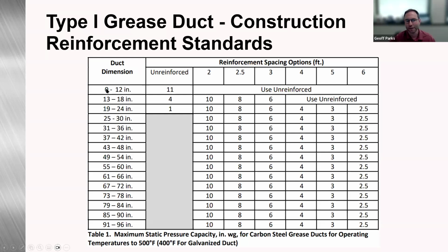So for instance, if you have ductwork built at 16 gauge carbon steel, 12 by 12, unreinforced, that can meet a capacity of 11 inches water gauge, versus 13 to 18 inches unreinforced would only be 4-inch water gauge. Once you start adding reinforcement, 2 foot, 2.5, 3 foot, these are the pressures that those panels will handle with that reinforcement spacing option. So it's a little different than the duct construction standard tables.